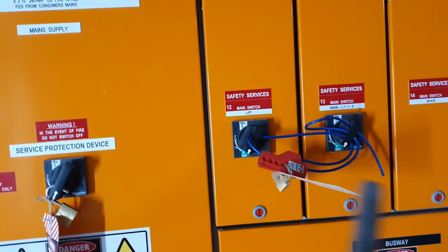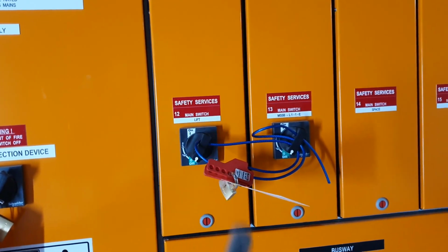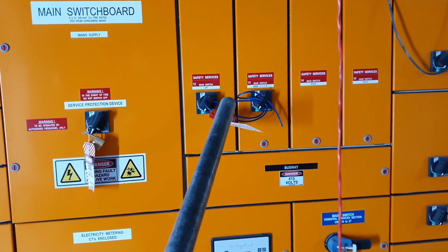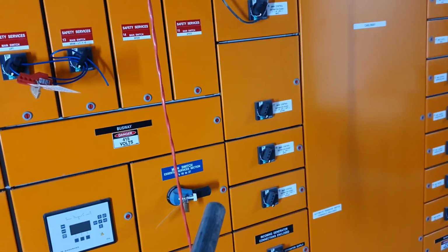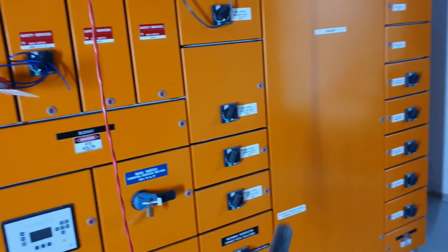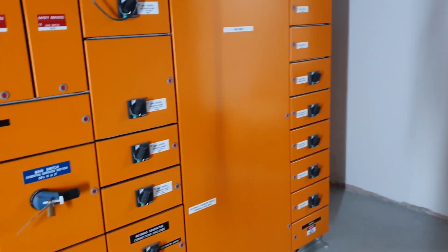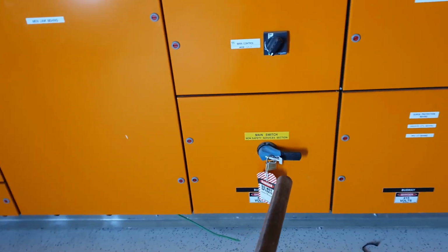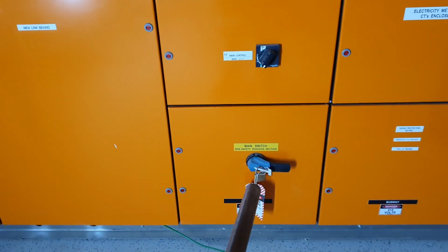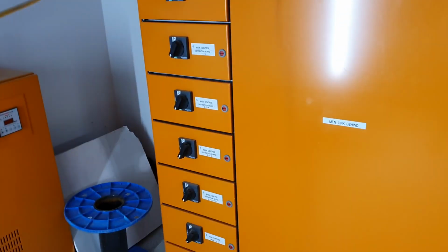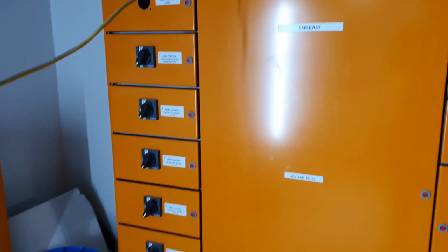I've locked off the mains here - the safety services, obviously, because it says it right there. The safety services will be live when that is live, so I've got to lock them off. I've locked off the essential services, which locks all those MCCBs off, and then locked the non-safety services, which is all these breakers here, so I didn't have to lock them all off individually.